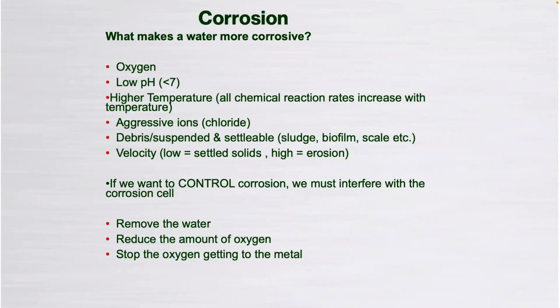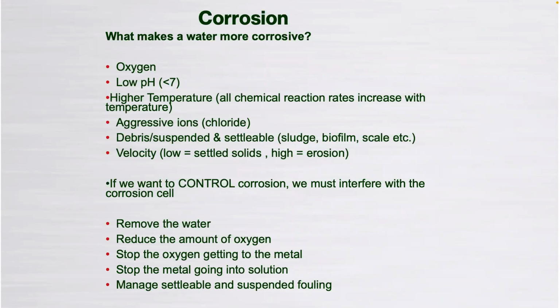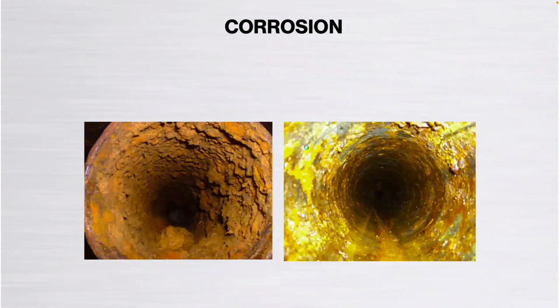You see those typically, certainly in the UK, on district heating networks. We need to stop the oxygen getting to the metal as well. So really that's where your corrosion inhibitors do their job. They lay a microscopic film to stop that happening, or stop the metal going into solution altogether. And that could be down to the types of materials that are available. And we need to manage settleable and suspended fouling. So through filtration, really, ultimately, it's very important that we have the right amount of filtration in our system.